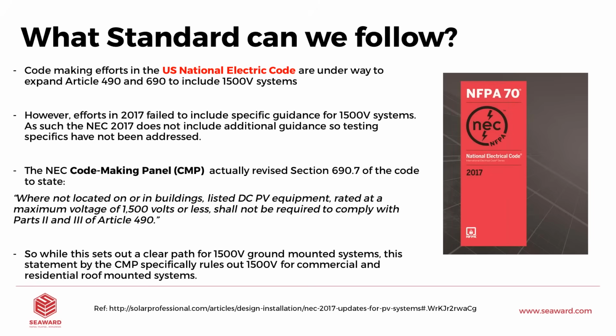Where not located on or in buildings, listed DC PV equipment rated at a maximum voltage of 1500 volts or less shall not be required to comply with parts 2 and 3 of Article 490. So what we can take from that is that while the panel is trying to set out a clear path for 1500 volt systems, there is really no regulation in regard to utility scale and ground mounted systems right now for 1500 volt. Now that helps us in some ways, so we're not hampered by rapid shutdown requirements, etc. However, there are new challenges that we face, and I'm going to cover some of those in this presentation.